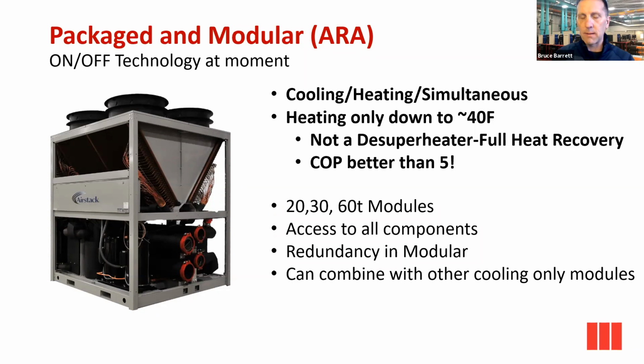You can figure out your building loads, your simultaneous need, and just use one of these ARA modules to do your max simultaneous load. You've got that built-in redundancy across the same modular concept. We're getting great COPs in that simultaneous mode, better than 5, really depends on the temperature and glycol percent. I do want to point out that we can make, say, 120, 125 degree water, all the way up to 130, again, depends on glycol percentage, etc., all the way down to about 40 degrees Fahrenheit. In other words, we can only extract so much heat back through the coil from the air, add a heat of compression, and make that quality of water. Okay, so that's one of the drawbacks. But by far, on the coasts and certain municipalities that are requiring it, or customers that don't have any gas on their job site, this is the #1 machine that they're applying in that market right now.